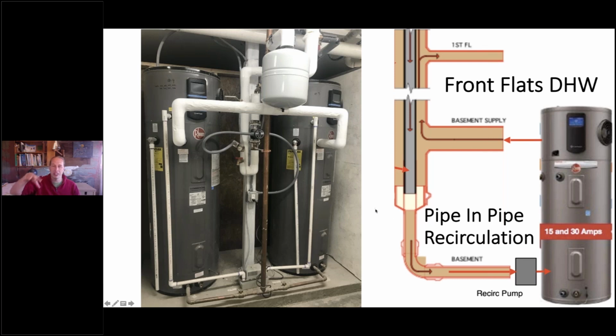So they've got 160 gallons of storage and then 2 compressors. Those are 5,500 BTU per hour compressors. And they're down in the basement. So they're kind of doing a ground source heat pump through the air of sorts. Best practices, really inexpensive, very stable, easy to take this tank out and replace it with a different one. The bigger the system, the more complicated it is, the harder it is to maintain, the more difficult it is to deal with when it fails.